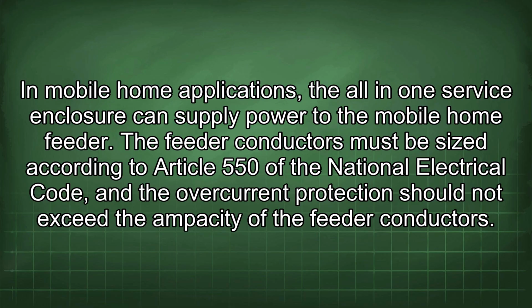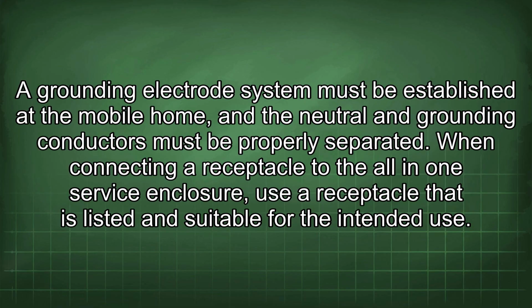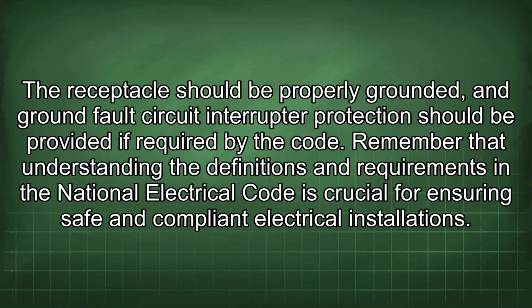The feeder conductors must be sized according to Article 550 of the National Electrical Code, and the overcurrent protection should not exceed the ampacity of the feeder conductors. A grounding electrode system must be established at the mobile home, and the neutral and grounding conductors must be properly separated. When connecting a receptacle to the all-in-one service enclosure, use a receptacle that is listed and suitable for the intended use. The receptacle should be properly grounded, and ground fault circuit interrupter protection should be provided if required by the code.